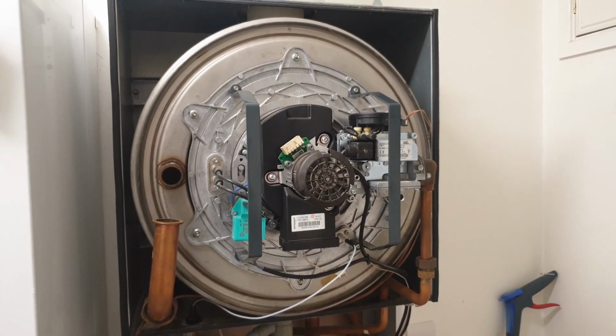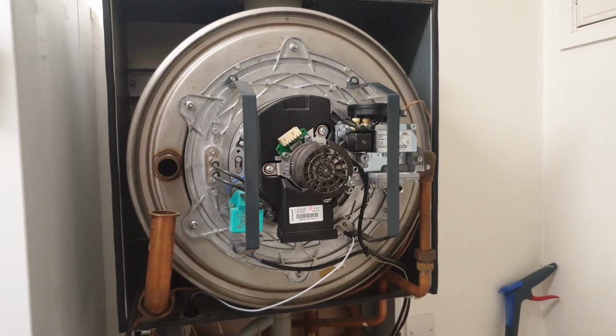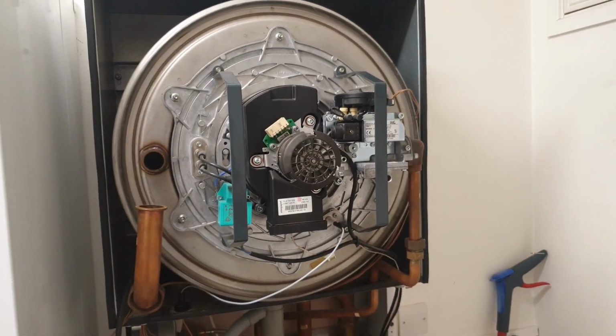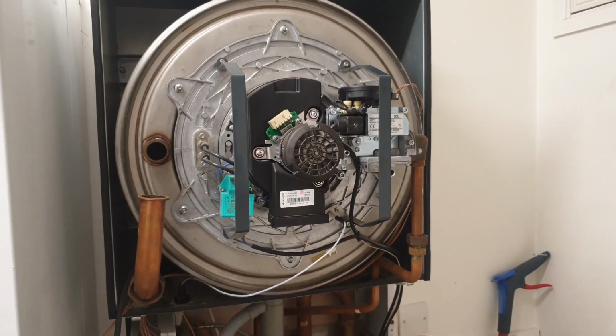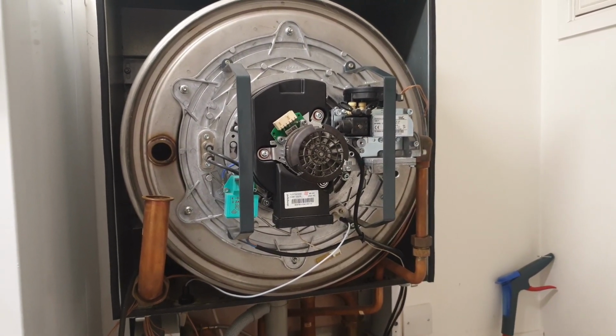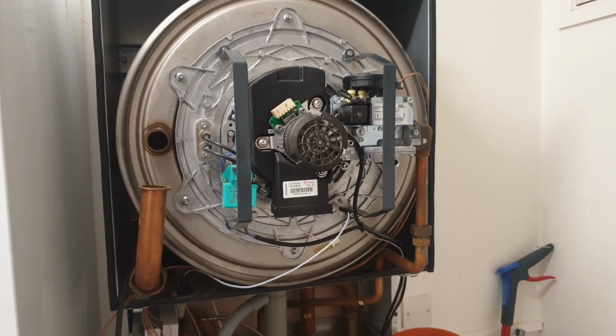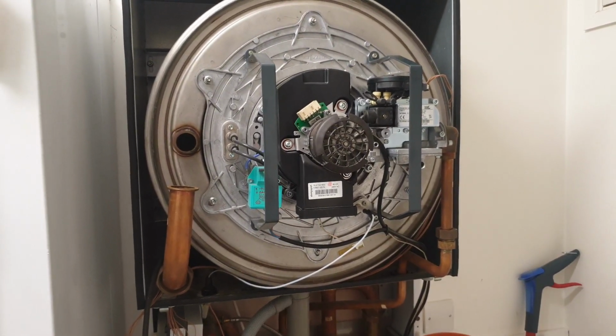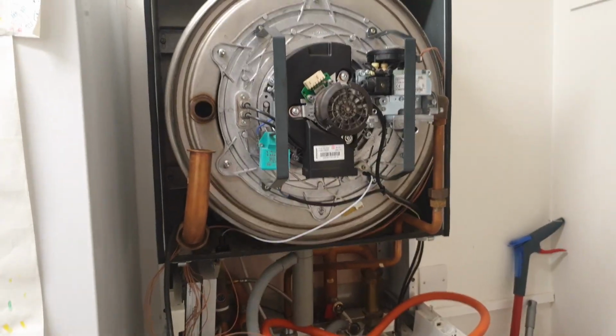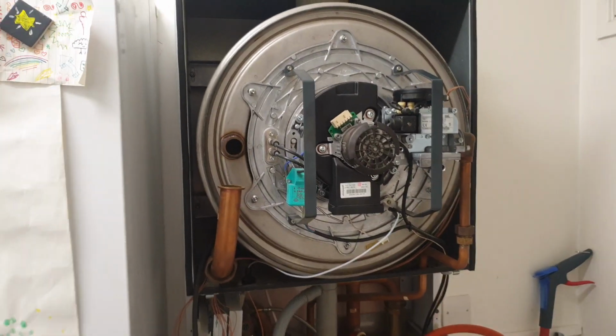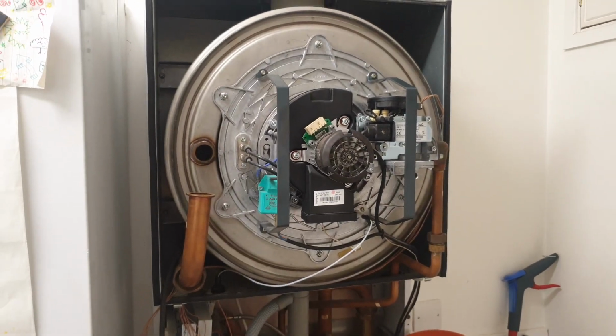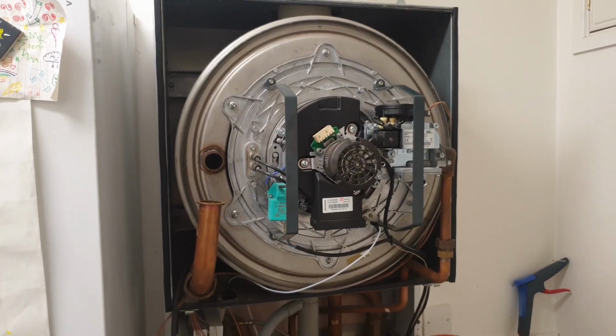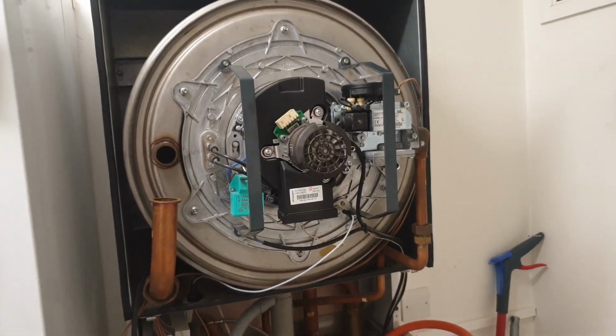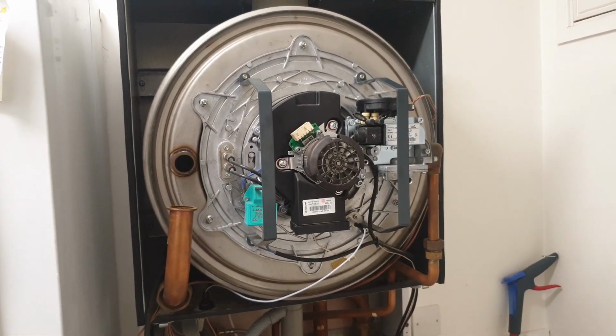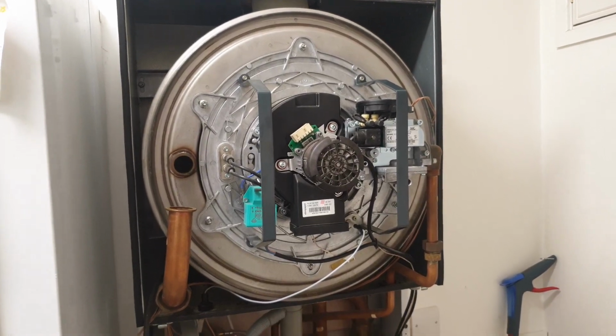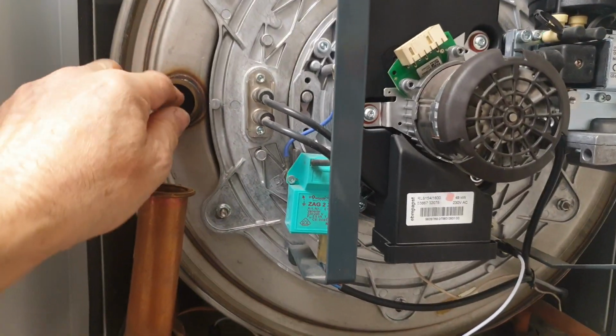Now, again, it's a limited sample group. It's my own personal experience. I'm sure other people have seen blocked plate heat exchangers, but I have not. So I've been going back to my plate heat exchanger jobs, finding almost always a clean boiler. I had a couple of instances where I went back and found the boiler was still dirty. I hadn't cleaned it enough in the cleaning process before fitting the plate heat exchangers. But not scaling, and certainly not blocking of the plate heat exchanger. So it does seem to be a successful method of protecting the boiler and preventing this localized scale.